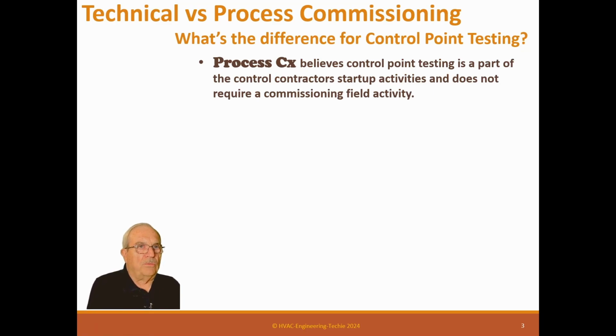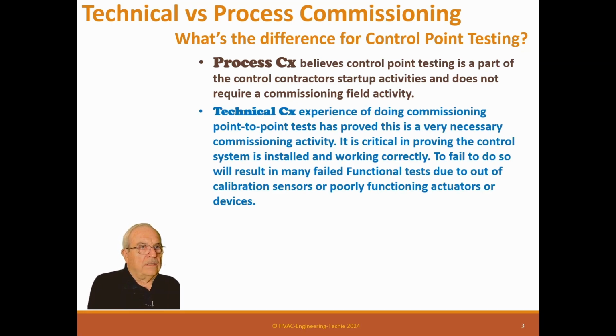Process commissioning believes control point testing is part of the control contractor startup activities and does not require commissioning field activity. Technical commissioning experience of doing point-to-point tests has proved this is a very necessary commissioning activity. It is critical to proving the control system is installed and working correctly. To fail to do this results in many failed functional tests due to out of calibration sensors or poorly functioning actuators or devices. It's really important. And when you're doing maintenance on a system, you do a point-to-point anyway. So I don't understand why people would not do this. It's extremely beneficial. It's a great teaching tool, and it actually makes the system work.